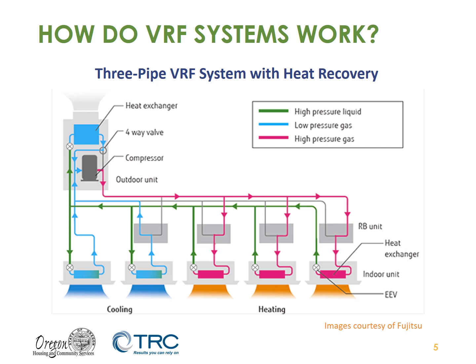In these heat recovery systems, however, that waste cool is utilized inside the building in order to cool a different zone. Essentially, a way to put this is an indoor unit requiring heating will open its hot gas or high pressure line and its liquid line valves and will act as a condenser so that we're releasing heat into the unit and waste cooled has to go somewhere. While instead of putting the waste cooled outside, we're able to use this high pressure liquid line to potentially produce or release the cool air into the building.